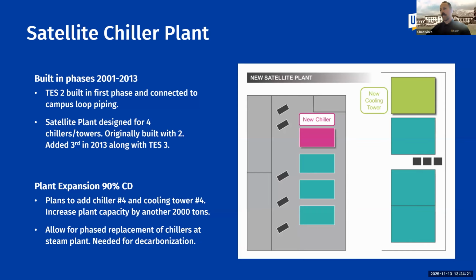So we're going to go back in, hopefully retrofit that diffuser system to match TES2 so it can flow and it can work in parallel, independent as needed, as designed, actually. So once complete, our chilled water system will have a total of over 14,000 tons of chiller capacity and over 60,000 ton-hours of storage, chilled water storage capacity, which is great.